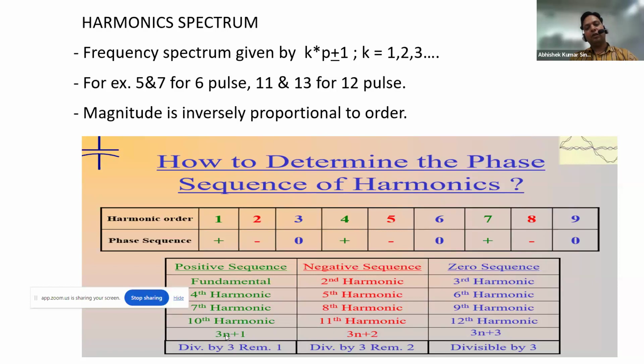You just have to put the number, just put 1. So 3 into 1 plus 1 is equal to 4. So 4 is the positive sequence harmonic. Just put 1, 3 into 1 plus 2, it means 5. So 5 is the negative sequence harmonic. 3 into 1 plus 3, it means 6. So 6 is the zero sequence harmonic. So let's come further. I believe this is clear to all.